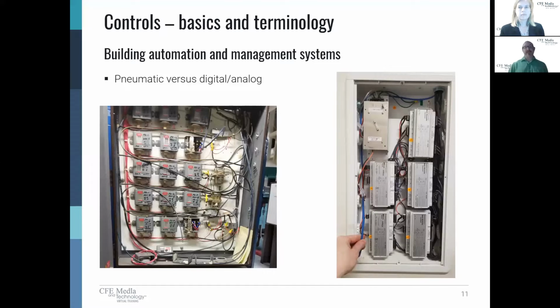Shown here is an example of the old versus the new. On the left, we have what's called a pneumatic system. Now, this is specifically for an air handling unit, and these pneumatic points were controlling dampers and air handling unit shutdown. Now, we had to move this thing. So are we going to really reuse a 30 or 40-year-old pneumatic system? And the answer is no. We're going to actually migrate all those points to digital because we already had a modern building automation system.